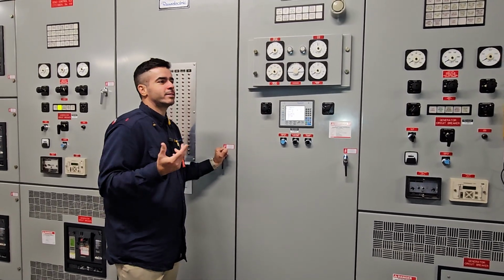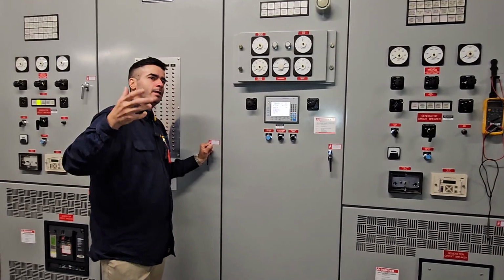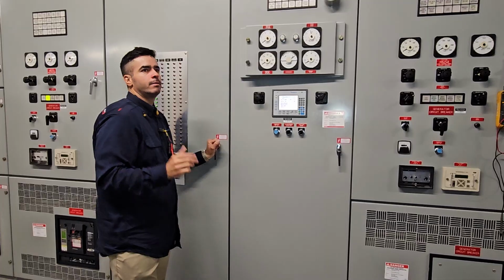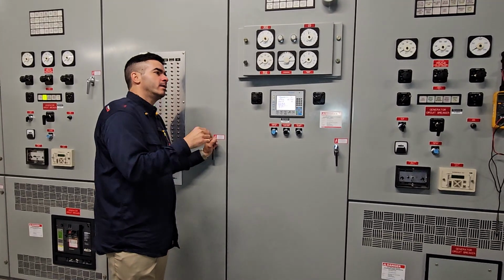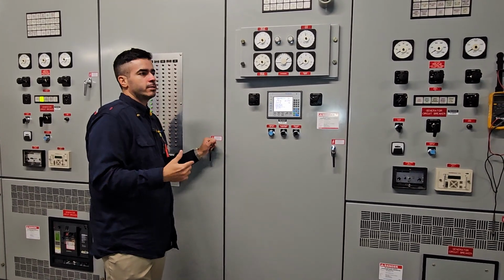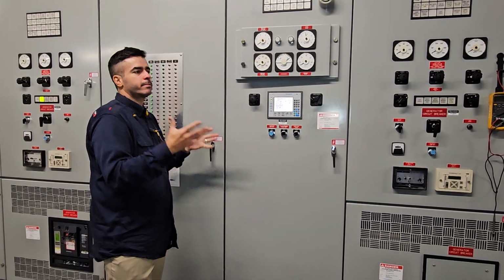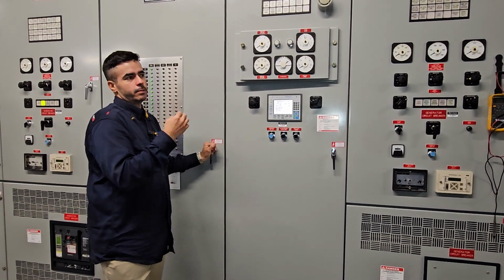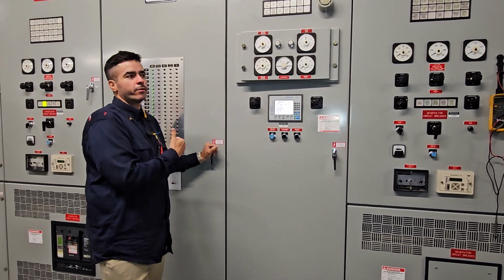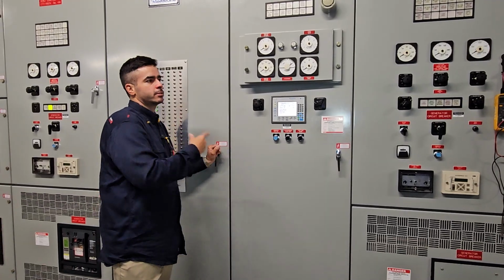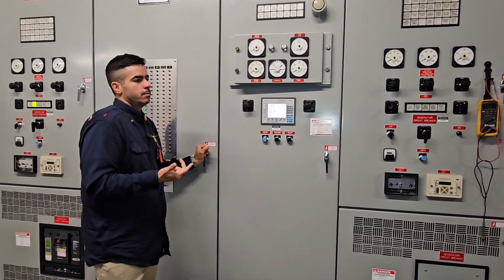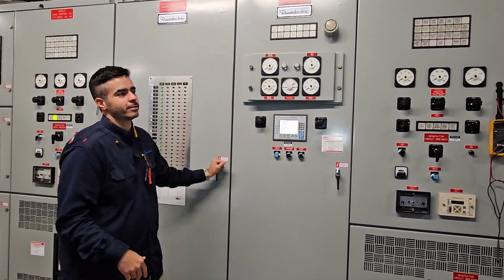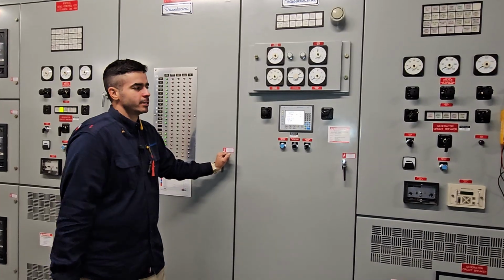So it's kind of a bad situation there, because the newer systems have their controller connected straight to the bus, because you want to be sensing that power, right? Back in the days, they were too afraid of connecting little electronics to 480 volts, right? They didn't have all the new technology that they have now with the microchips and stuff. So they were afraid of frying something by putting 480 volts into the controller, so they would just use that other method. But eventually it will fail, like everything else, right? But yeah, that's basically the issue.